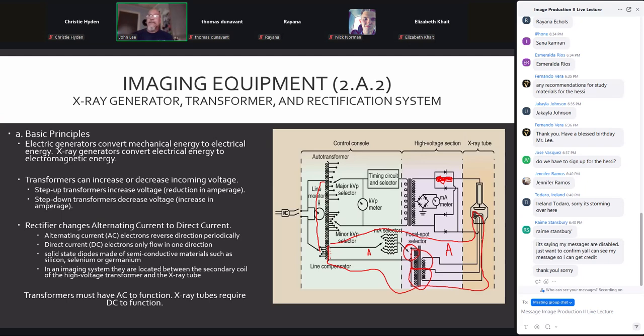Now, that takes care of the first part. When we go to rotor up, that activates the filament circuit. So the current starts to flow, the filament starts to get hot, and the rotor starts to spin because of the stator and that induction motor. The second part of the exposure, pushing the button all the way down or pressing the other button, activates the timer.